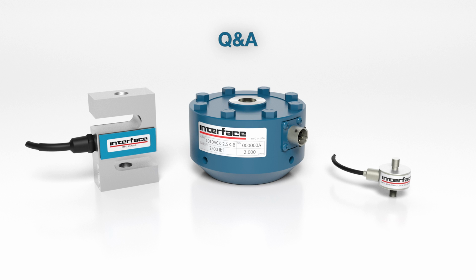Fundamentally, the sensors will work all the way from 0. They're going to respond. It's an analog device. The problem is that it can often yield less confidence in that measurement at the low range. But oftentimes we can overcome that with extra calibration points. We're more than happy to do low range points and provide you the actual data on that, which you can then often load in your instrumentation and use that to take out any nonlinearity concerns too. So it depends. Sometimes it's unavoidable and you need to work in that low range of a sensor, and we do have some options to help you get the best data possible there.